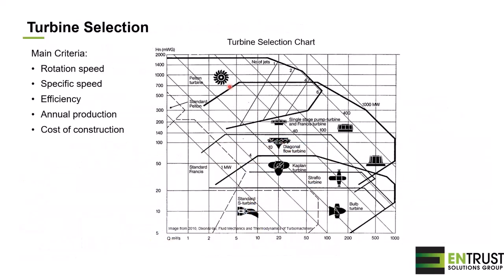If we summarize all these turbine types in a chart, we will find something like this. A turbine selection chart where we find, for example, on a high head project with low flow, the Pelton turbine, and on the opposite, on a low head project with high flow, we can find a Bulb turbine or a Kaplan turbine. The Francis are usually in between. The main criteria when doing a project is to select a proper rotation speed, to select the best way to extract the efficiency, what annual production we want to achieve, and the cost of construction.